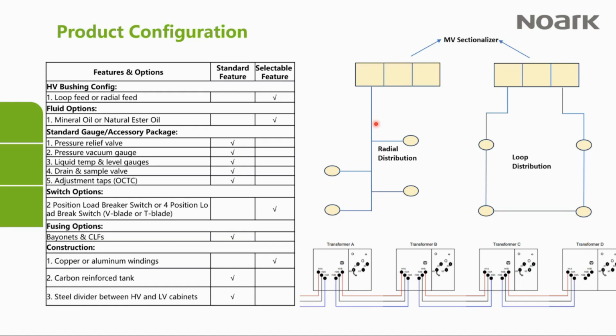So you can have that. And typically this kind of distribution system, you find it more in remote locations, right? Where maybe reliability is not really a big issue. So you don't have a redundant system here compared to the loop distribution. In the loop type, you can see that you have two supplies in this picture. So it's the same pad mount transformer, four of them in a loop distribution. So it goes from one transformer to the next one, to the next one, to the next one, and then back to the supply, so that you have a loop distribution.